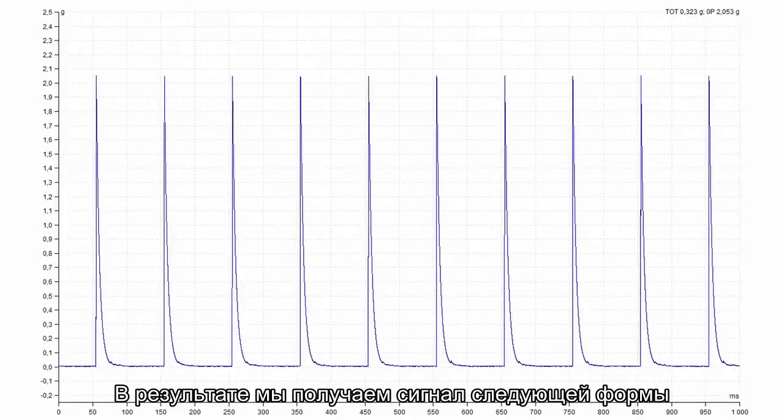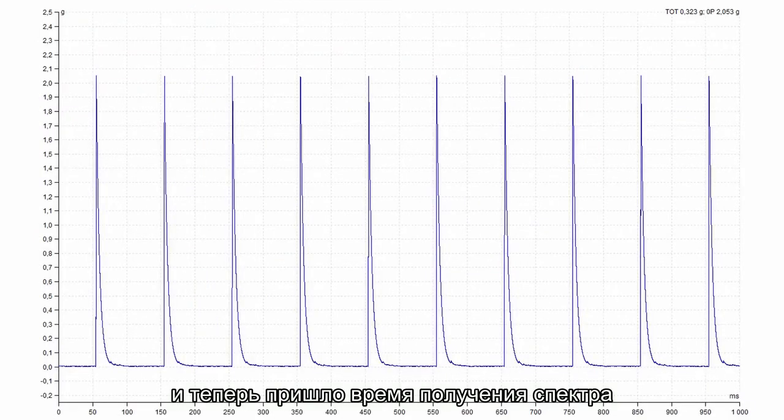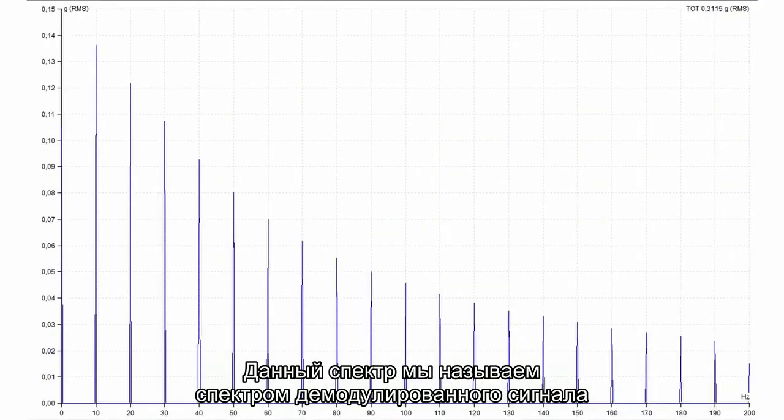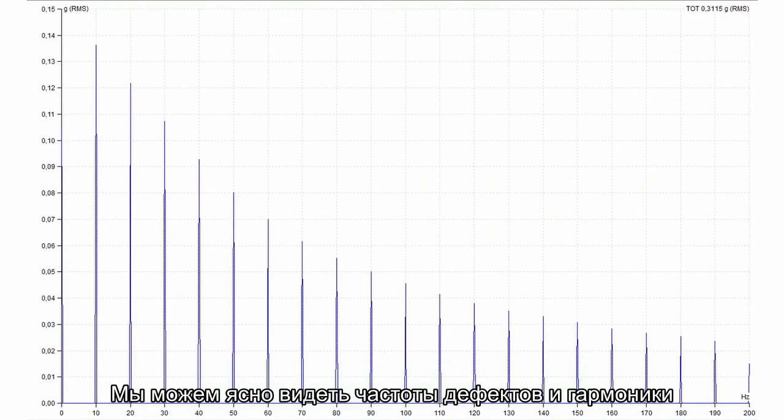After enveloping we received this signal shape. And now it is the time to apply the spectrum. This spectrum we call demodulation spectrum. We can clearly see the fault frequencies with harmonics.